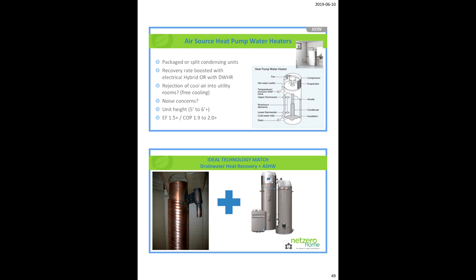Seriously—now with units like this, the new systems, the really efficient CO2-based systems, now have duct kits, which is fairly new. They didn't used to want you to put a duct with the rejected cool air coming off; they wanted it to stay in the room because they were concerned about freezing the coils internally. Now the new systems come with a duct kit.